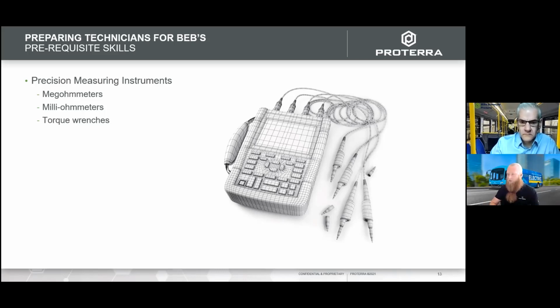Going back to the bus bar conversation about using the right tools for the task at hand, if I made a repair using those bus bars and then tested with a milliohmmeter, and I had scored that bus bar by using the improper tool, there's a strong possibility it would give incorrect readings for what the actual resistance value should be. Again, we want it to be pretty low.